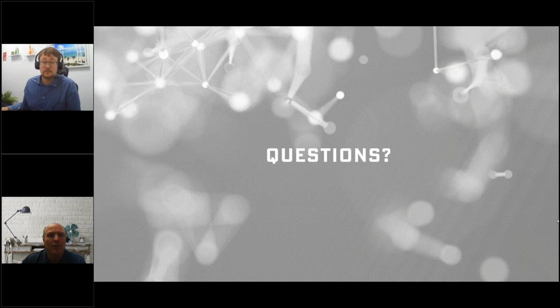All right, very good. I see a question from Bill. With MPPTs, is it better to max the voltage or the amps inputs? And he says with PWMs, I assume the amps should be max, as it's going to cut off the voltage anyway. And the answer we have here is that with MPPTs, you actually want to max out total power. That's voltage times current. You do need to be careful with some MPPT controllers, as the current rating of an MPPT is its output rating and not the solar input rating, which may be lower because it allows a higher voltage. So that gets into the DC conversion that happens with MPPT controllers. Thanks for that question.